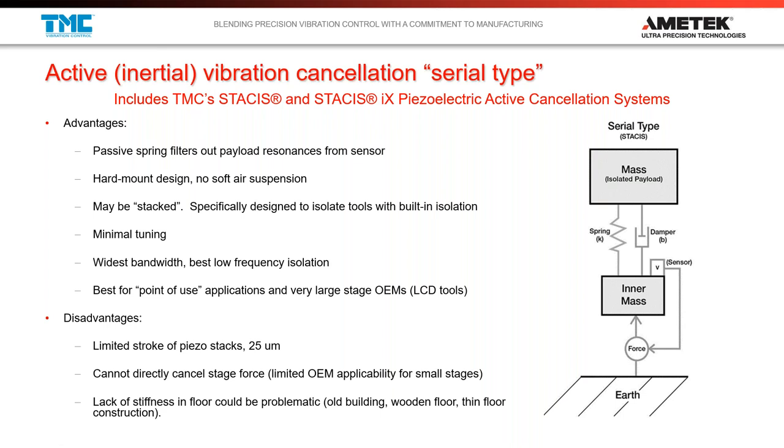The very high level takeaway is that this entire system uses no soft components. Piezoelectrics have very, very high resonant frequencies. The spring that supports the payload has a relatively high resonant frequency. And therefore, there are really no low frequency resonances feeding into the system, which gives you quite a lot of bandwidth available for broadband cancellation, especially at low frequencies where you don't have this superfluous input.